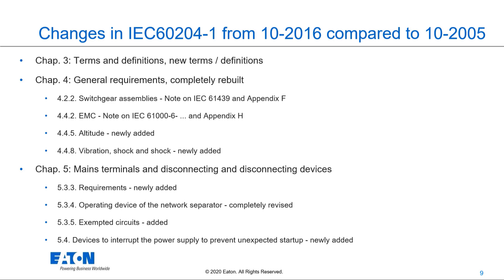Looking at the changes in IEC 60204-1 from 2016 compared to the former version from 2005: in Chapter 3, Terms and Definitions, new terms and definitions have been added. Chapter 4, General Requirements, has been completely rebuilt. Importantly, for switchgear assemblies there is now a link to IEC 61439. EMC measures and the new Appendix H are also linked in this chapter.